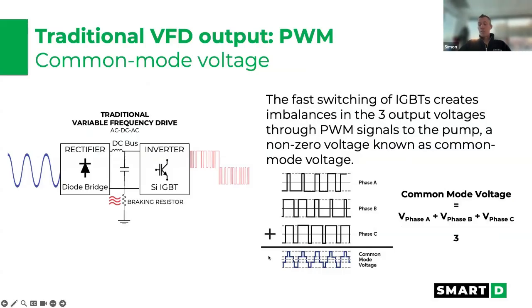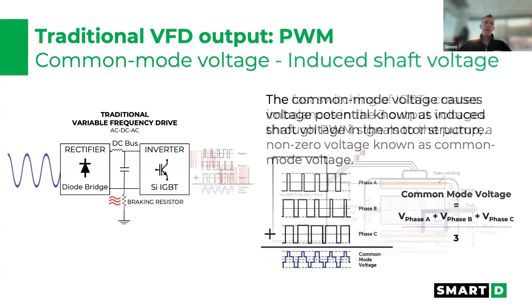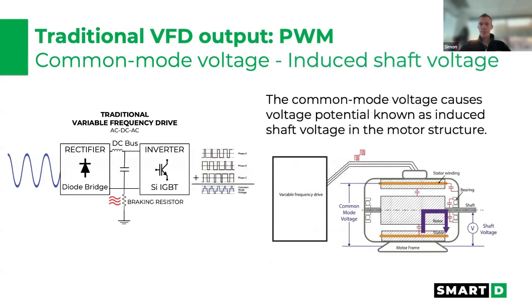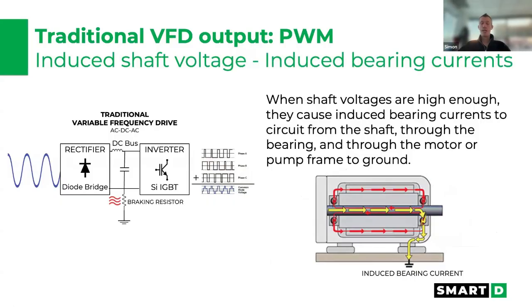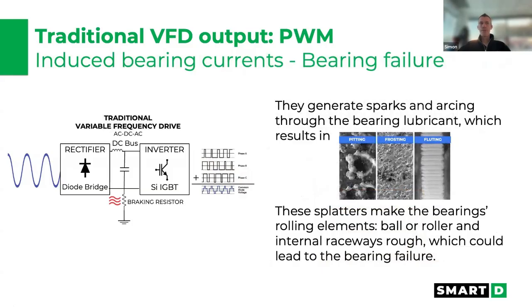This can actually be above 100 volt, and then it hits the motor. The motor wasn't intended for that. You create a voltage potential, which induces a current in the motor, which now needs to get out of the motor, goes through the shaft, through the bearing, and that is what is causing your pitting, frosting, and fluting.